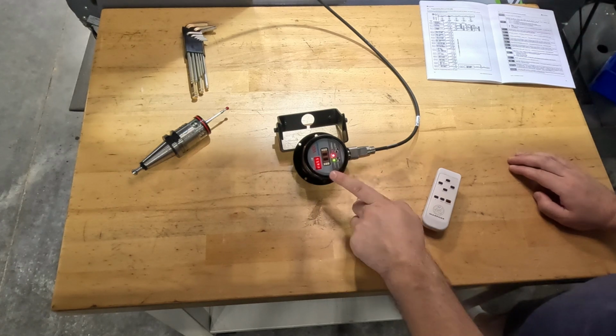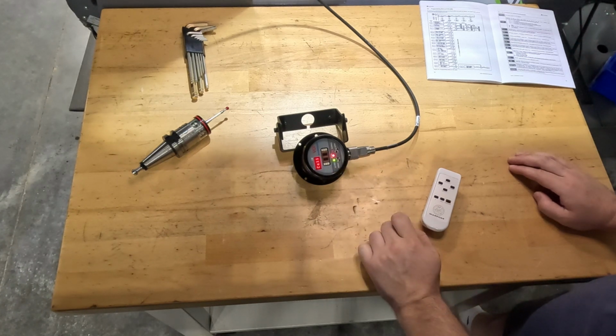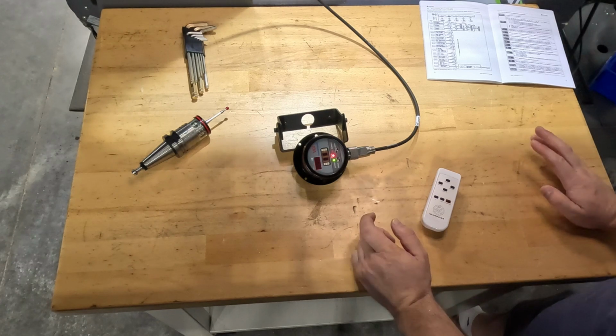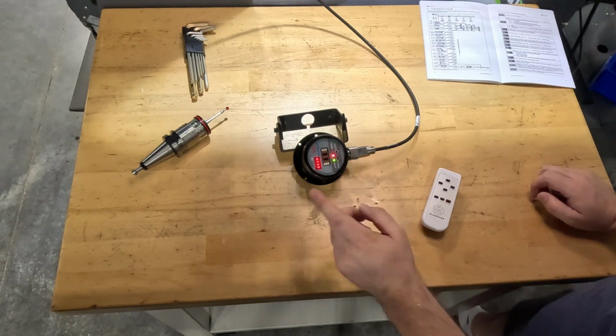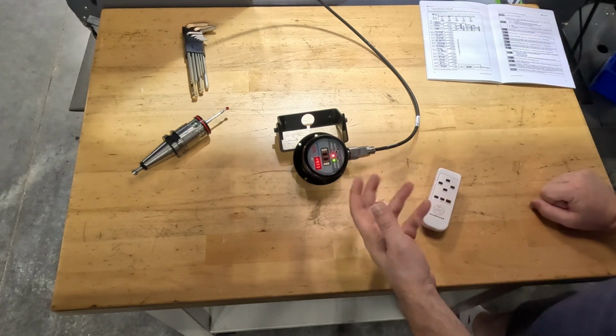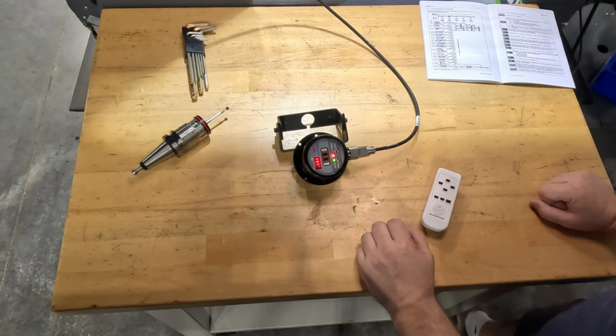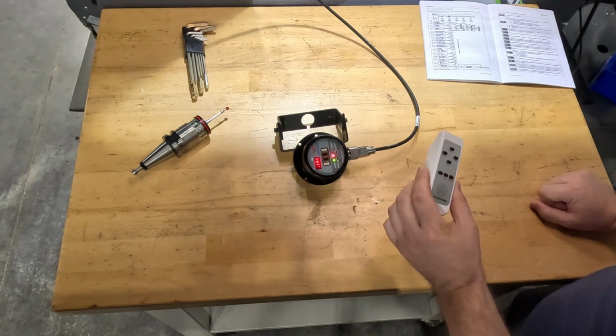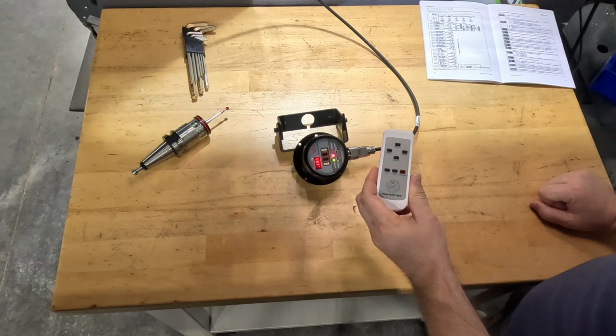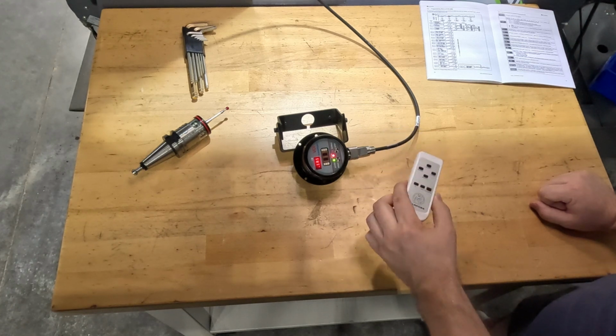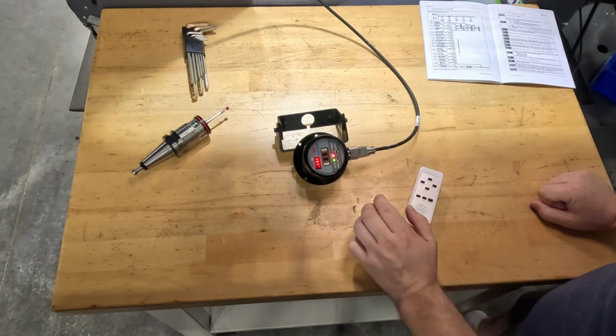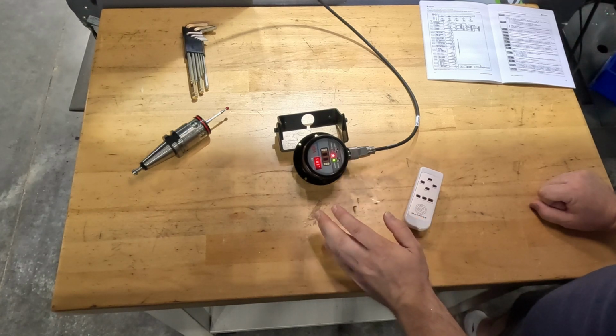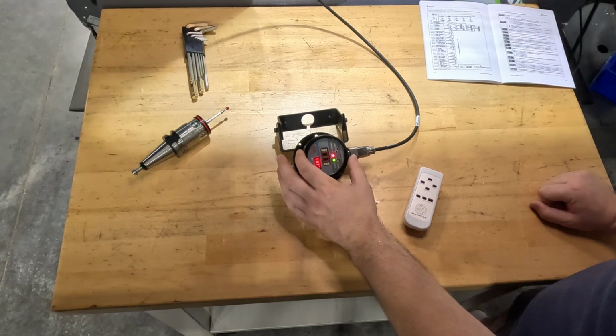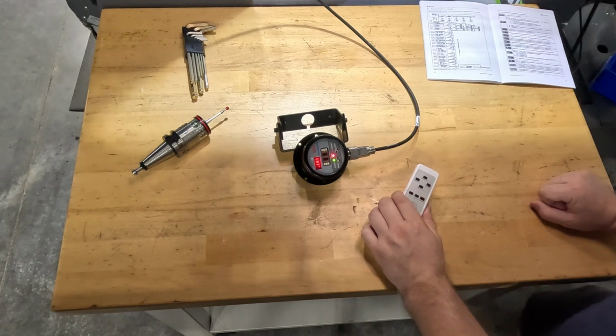When this is finished, the receiver will display either 1A1 or 2A1, just depending on whichever channel it's looking for, the probe or the ETS. And that's just waiting for a signal at that point. So to do the programming, there's a remote that Marposs includes in the kit. So we're going to use that. You can also use 2 buttons on the receiver as well. I'm not a fan of doing that because you have to take the cap off in order to do so.